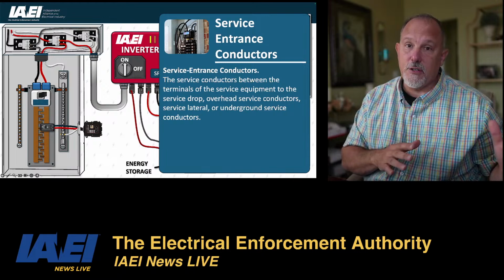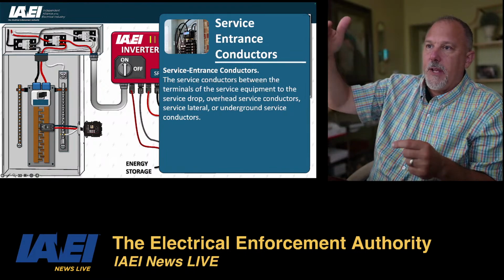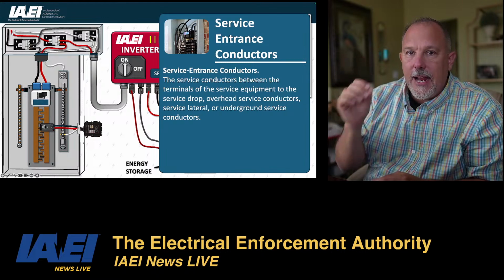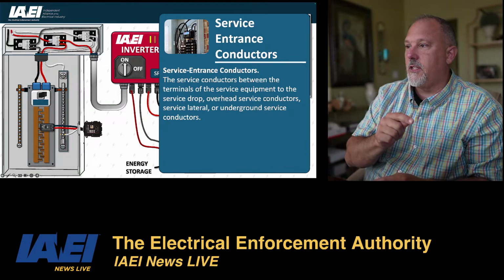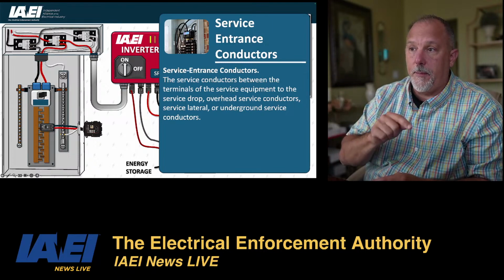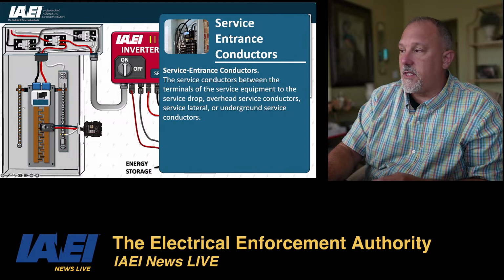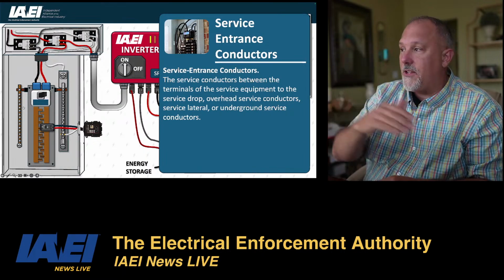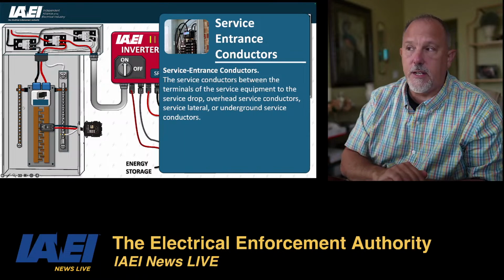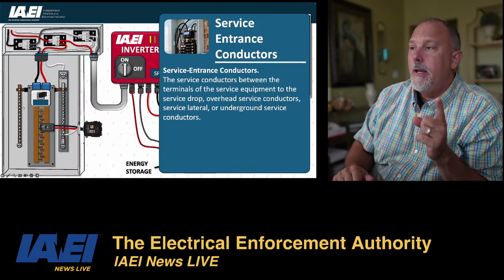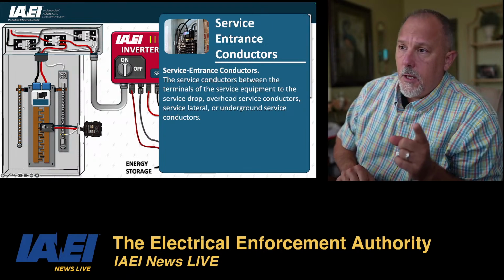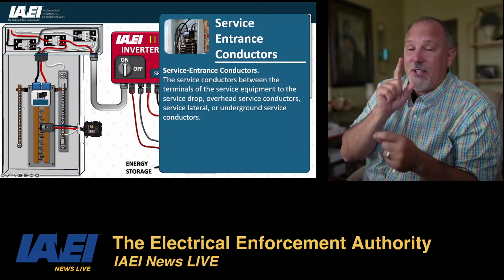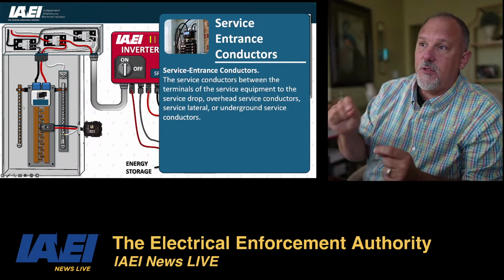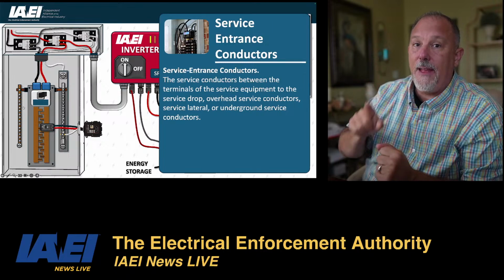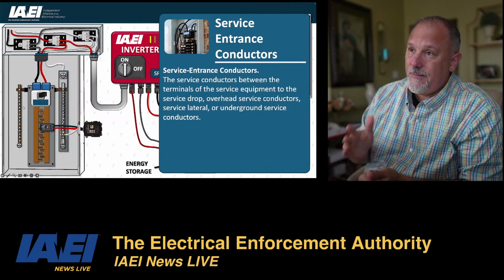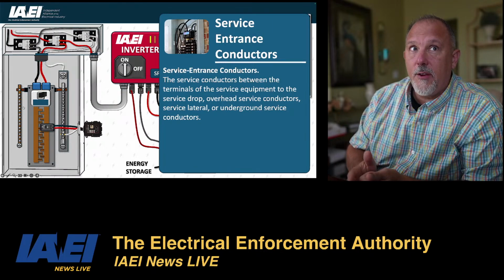And there's a defined term for service conductors. I go through all of those items. So service entrance conductors are service conductors that go between the terminals of the service equipment to the service drop, overhead service conductors, service lateral, or underground service conductors. And I'm going to show you those in a minute in a different diagram. But it's important to understand the definition of service entrance conductors, because when we get to those power distribution blocks and the section that governs it, you'll know where you can put those and where you can't.